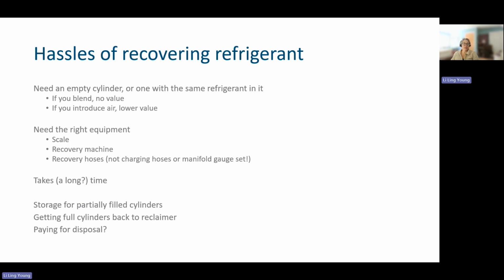We know it's a hassle to recover refrigerant. Here are some things that we're aware of that are a challenge, and if there's anything that we've missed, I definitely want to hear about it. One, you need an empty cylinder or one that has the same refrigerant in it as what you're recovering right now. Because if you blend refrigerants, they have no value. And if you introduce air into your cylinder when you're recovering refrigerant, it reduces the value of the refrigerant.